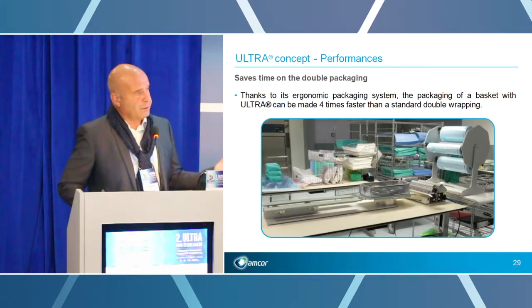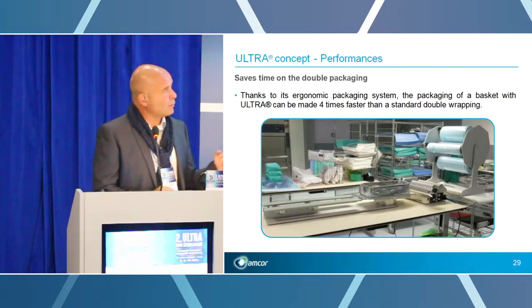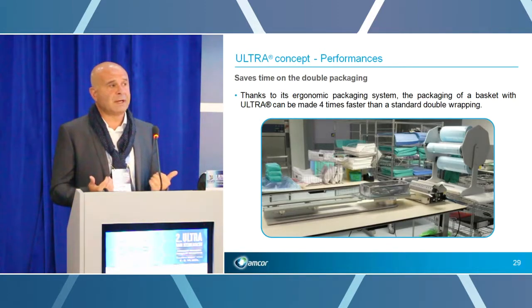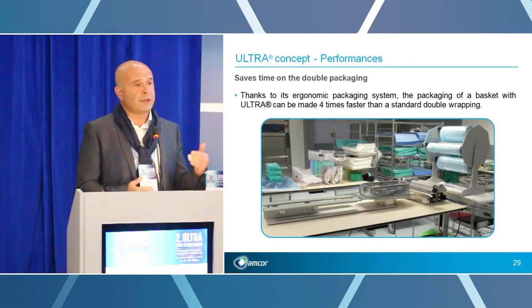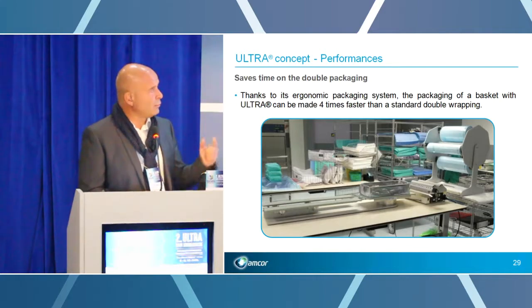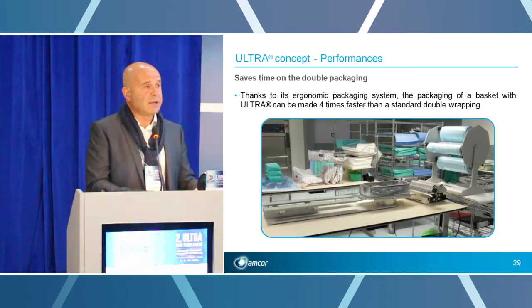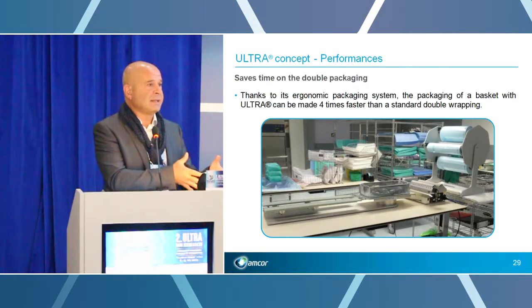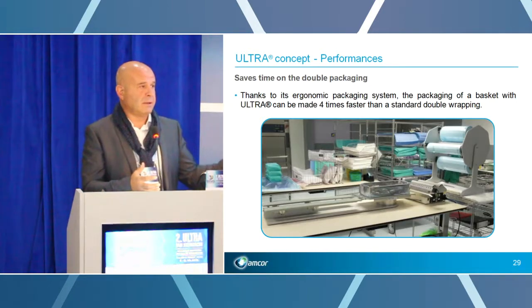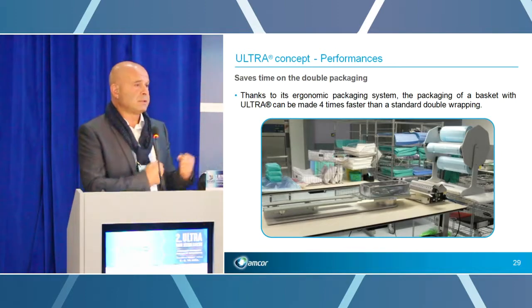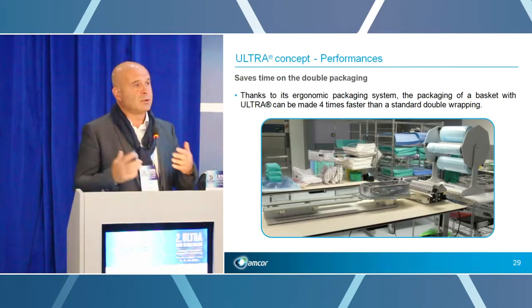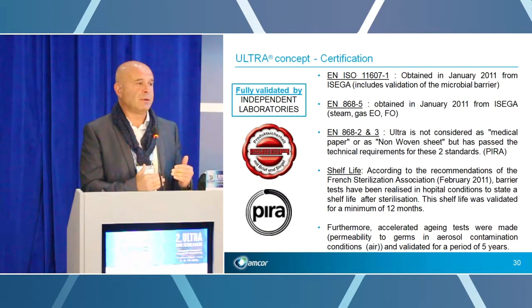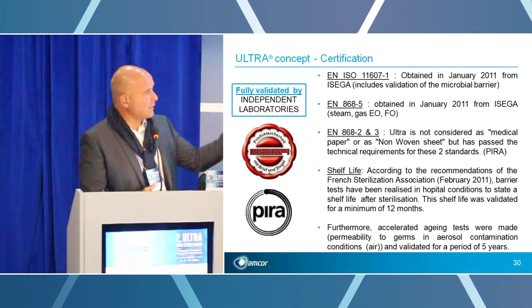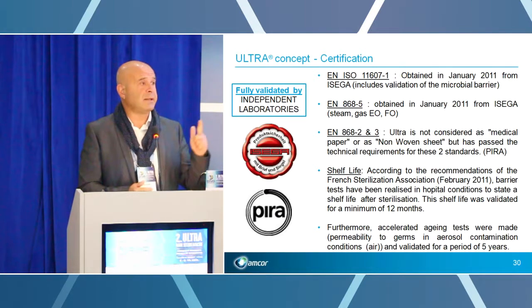We have conformity to all standards, and the very important part, after we started with this product, was to calculate the shelf life that we recommend. And we did this shelf life study with the president of the World Association. We decided to do the shelf life test directly in the CSSD. We put some packaging in a storage in the operating room, and every three months we took some packaging to the laboratory to verify if the medical device is sterile or not. And we did this test during 12 months with single packaging and double packaging.